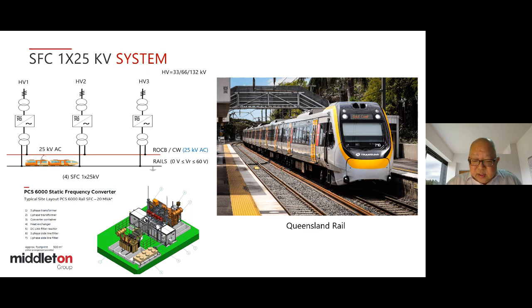EMC performance is also better than the classic rail return system, and as you can see, this particular train is fed from both directions, or from 2 or 3 adjacent static frequency converters. SFC requires smaller land size than transformer-based feeder stations. The high voltage balancers are not required because we are taking a 3-phase supply. The supply is already balanced, so you don't need to balance it. So there's no additional land or additional equipment required to balance the 3-phase supply. And of course, as I mentioned earlier, no neutral section required.